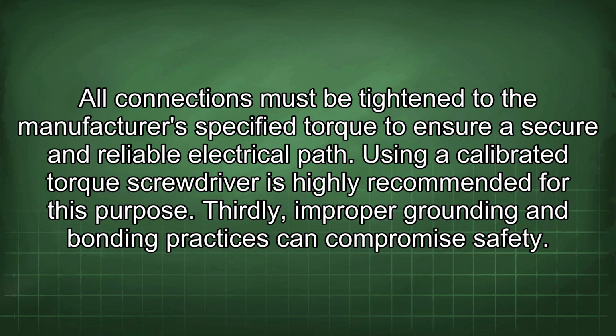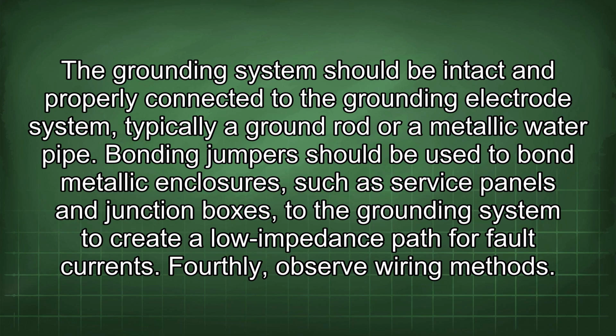Thirdly, improper grounding and bonding practices can compromise safety. The grounding system should be intact and properly connected to the grounding electrode system, typically a ground rod or a metallic water pipe. Bonding jumpers should be used to bond metallic enclosures, such as service panels and junction boxes, to the grounding system to create a low impedance path for fault currents.